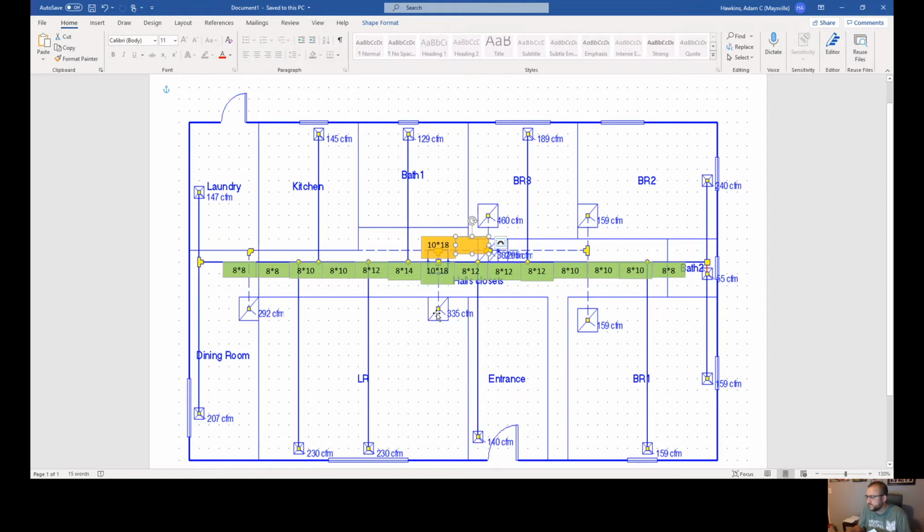And on this end, you're going to have a big one in the living room because it's a bigger space, and possibly one in the dining room or the hall. So in this case, let's just do the bedrooms on this. So 1, 2, 3. How big does a piece of duct have to be to handle 300 CFM at a 0.1 static?